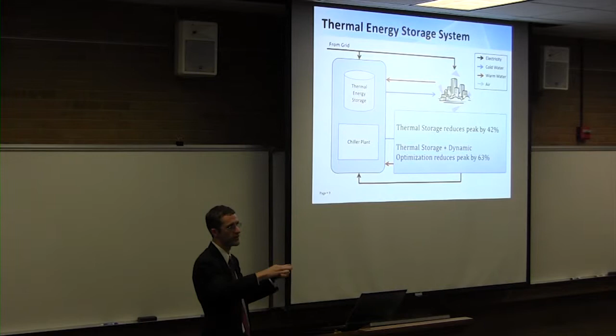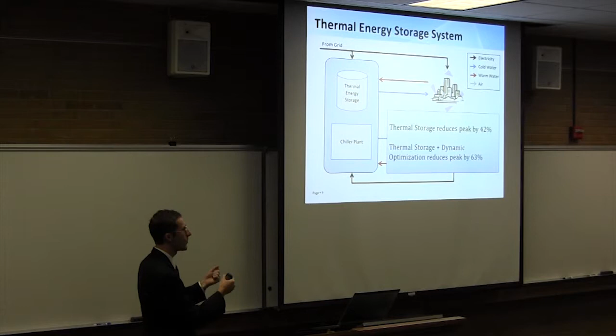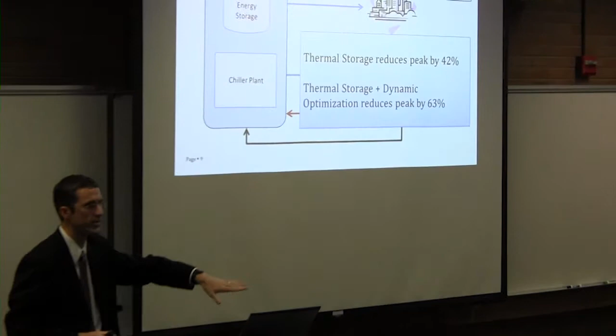To summarize the difference: if you just deploy thermal energy storage using heuristics, like knowing it's hot in the afternoon so that's when you use it, you get a lot of peak reduction savings. In this case, we could reduce the peak by 42% just by installing thermal energy storage. But if you install thermal energy storage plus dynamic optimization, you improve those benefits drastically just by operating the system in the most efficient way. We could improve benefits from 42% to 63%, just through intelligent management of the system.